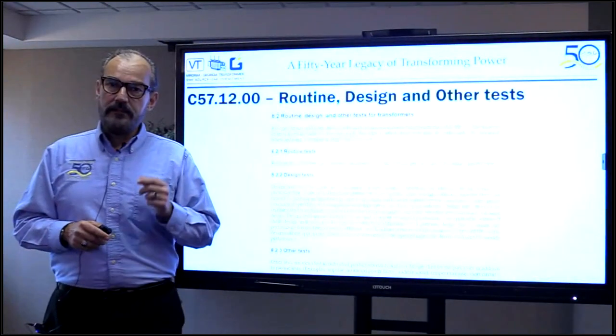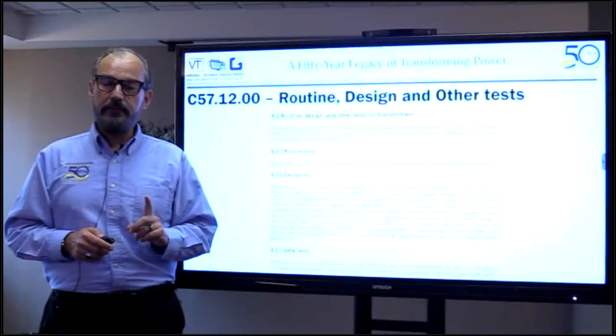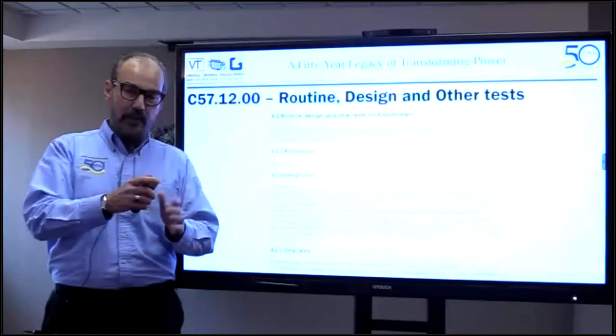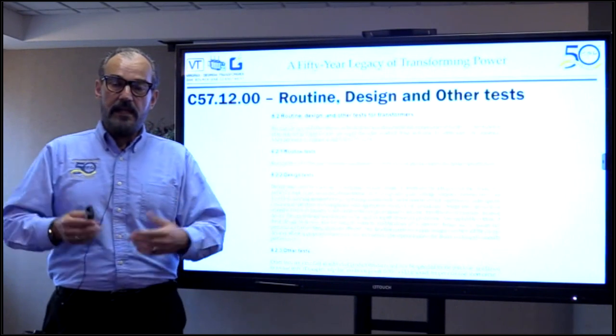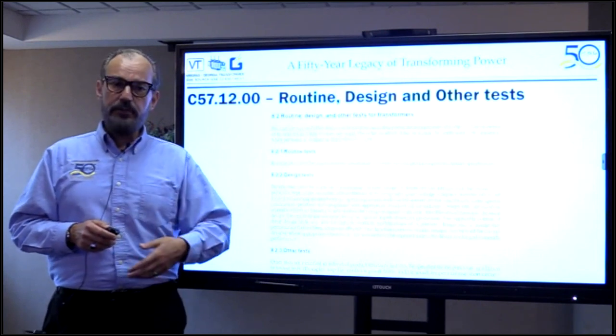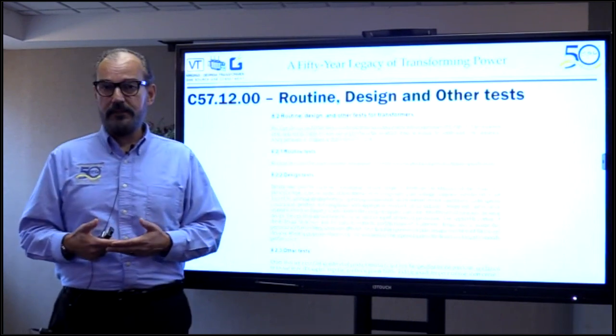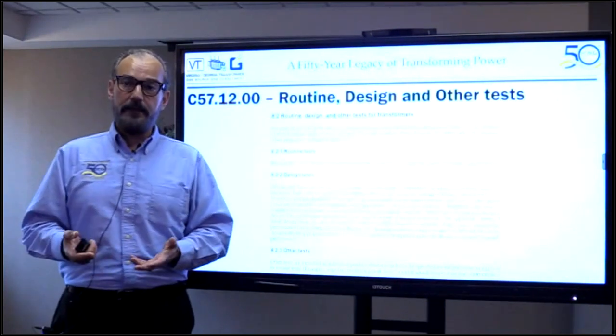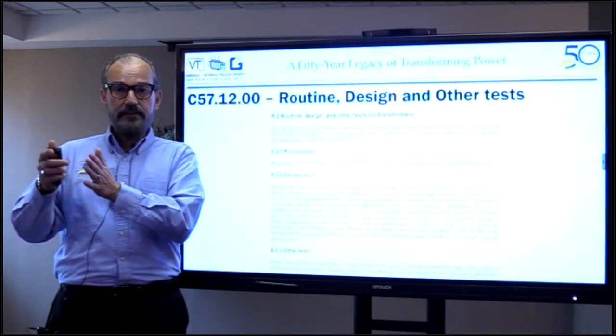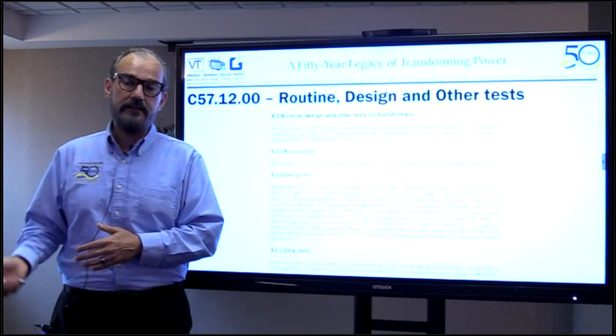Design tests shall be made on a transformer of new design to determine the adequacy of the design of a particular type, style, or model. If our company has already designed, built, and tested that design before, and you did not ask for it, we don't actually have to perform that test. However, if it is a brand-new design that hasn't been previously verified, we still must perform that design test.